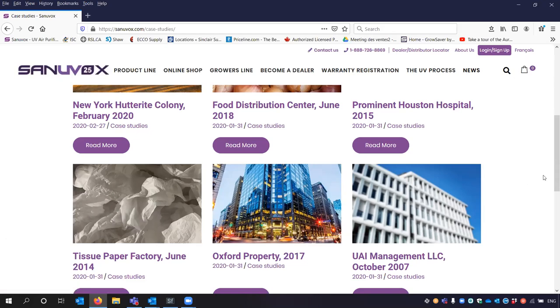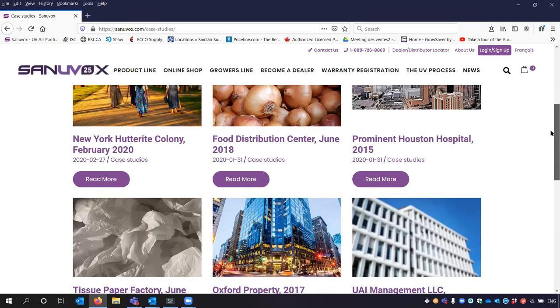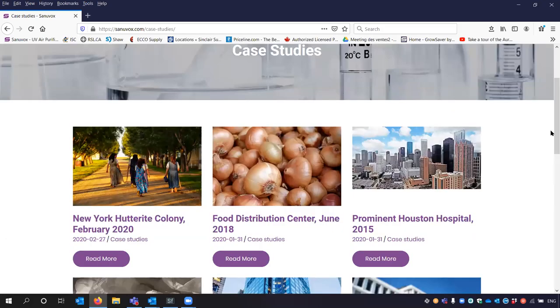Now, with coils as well, when we're talking about walk-in coolers or food banks, etc., a lot of fruits and vegetables, and even fresh cut flowers, degrade due to ethylene levels. So if we're sizing out a walk-in cooler, I will often size in a small portion of UV oxidation to keep the ethylene levels down, which dramatically increases the shelf life of the fruits, vegetables, and cut flowers.